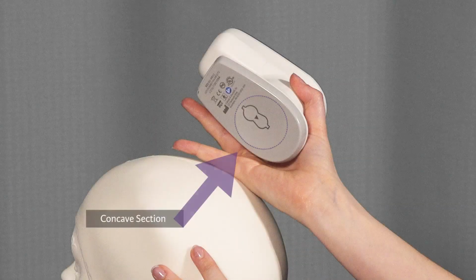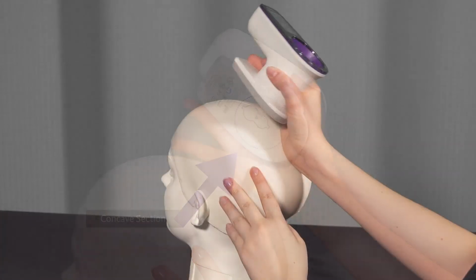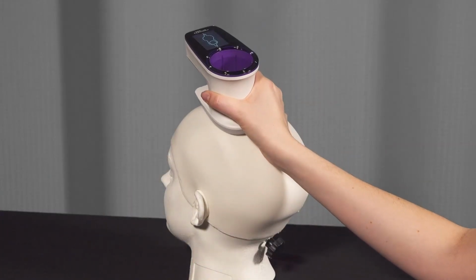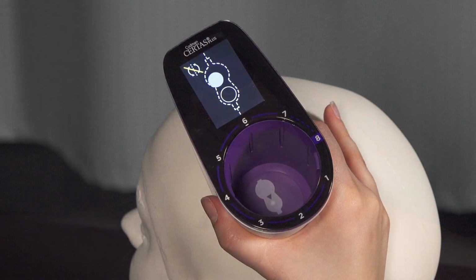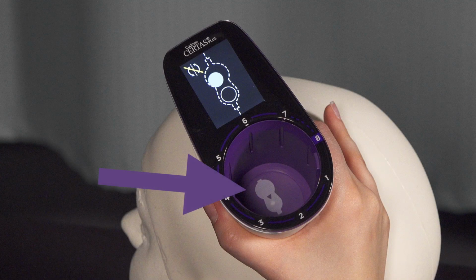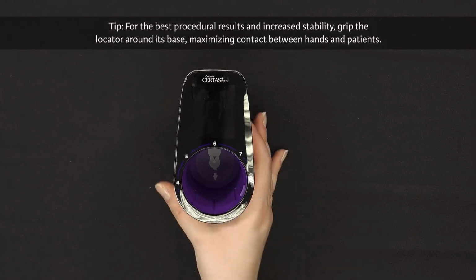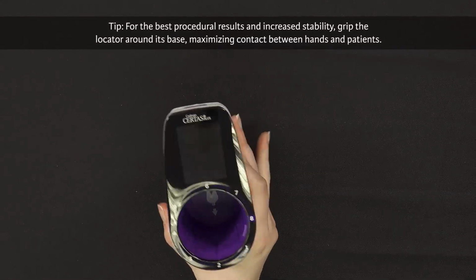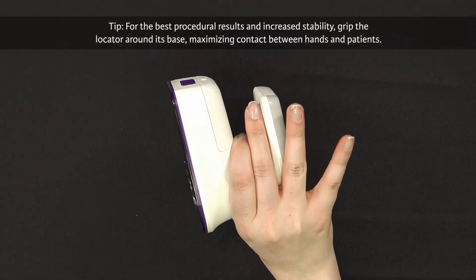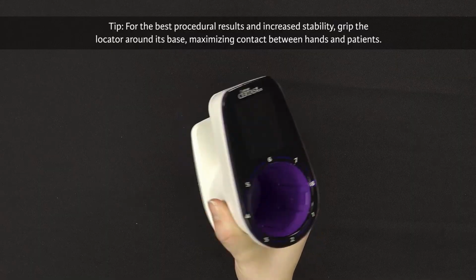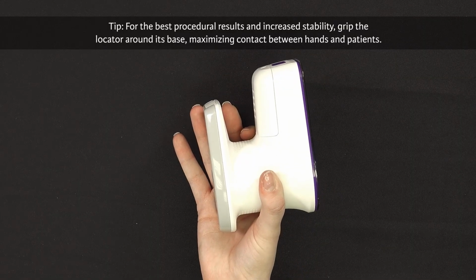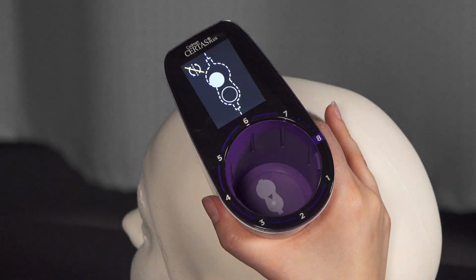Place the concave section of the locator base in contact with the patient and orient with the valve's direction of flow. A valve illustration is inside the adjustment tool cavity to serve as a reference for the valve. For the best procedural results and increased stability, grip the locator around its base, maximizing the contact between your hands and the patient. When in proximity of the valve, the locator will display the locating dot.